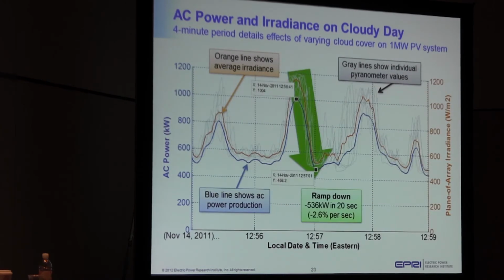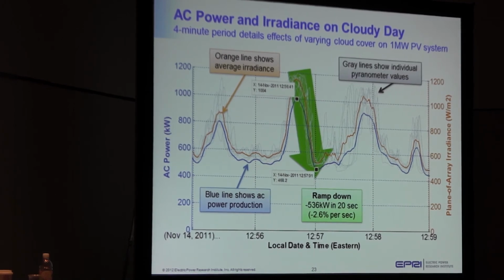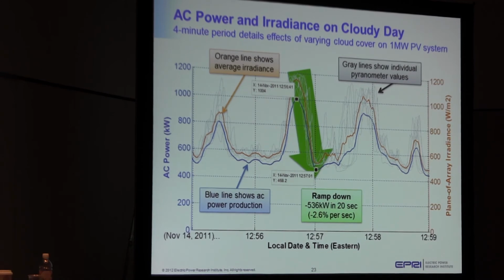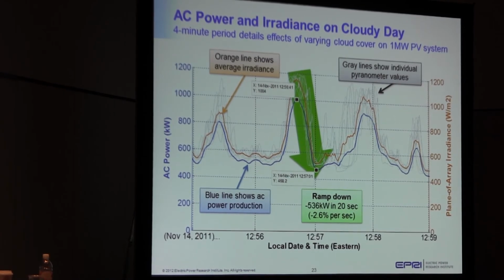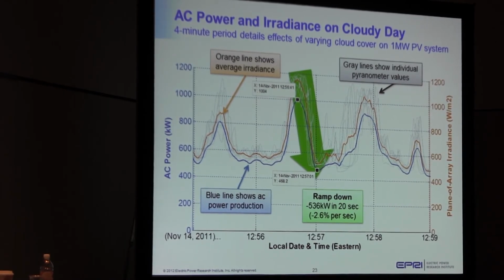I'm going to skip ahead and zoom in here, looking at 4 minutes. Remember we had 8 pyranometers scattered around the plant. You can definitely see a kind of wave effect as clouds pass over the plant. The orange line represents the aggregate irradiance from those sensors, the gray line shows individual pyranometer values. You can also see a good correlation between AC power production, the 1 megawatt output, compared to the aggregate of the 8 pyranometer systems.